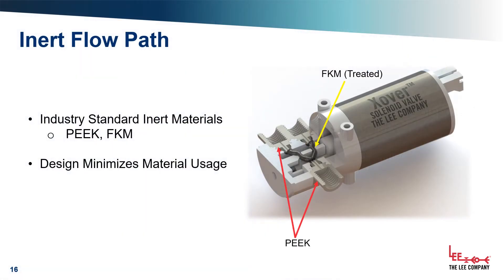If we had designed the best valve from an operability standpoint but without industry standard materials, it wouldn't be a good fit for the diagnostics industry. Therefore from day one we ensured that we were using tried and true materials known for compatibility in your applications. From the PEEK ports to the highly engineered FKM molded tube assembly, this valve will be easy to qualify in your system. You can see from the cutaway on screen how we achieved such a streamlined flow path with only two wetted materials.